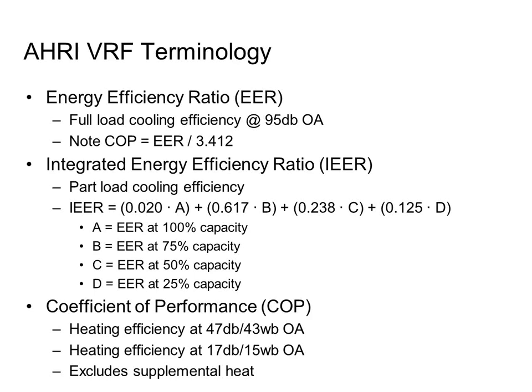Jeff asks about the significance of the 17 degrees for testing. The reason that we do it on heating systems, and this is for all heat pumps, not just VRF, we rate them at 47. And the reason it's 47, by the way, is that traditionally, a long time ago, when we had certain temperatures we expected indoors, that 47-degree rating point for heating gave us approximately the same delta T across the heat exchanger that a 95-degree cooling scenario would have given us. So that's kind of how that 47 number evolved.